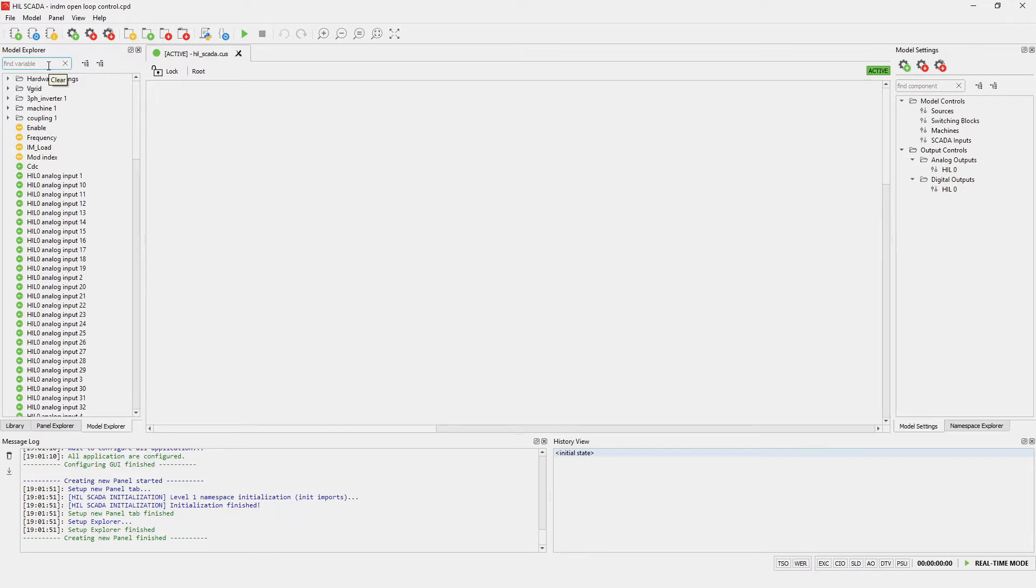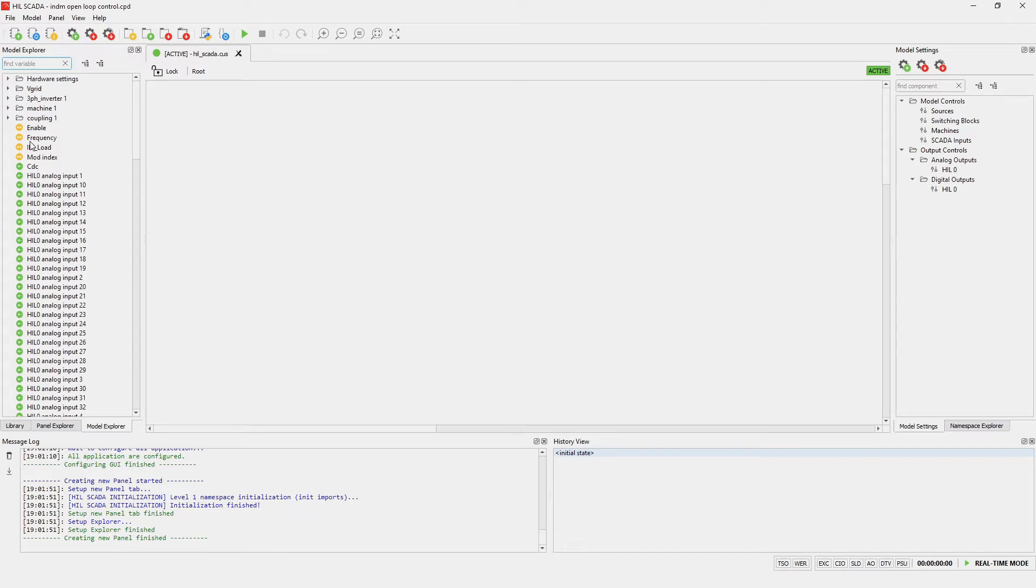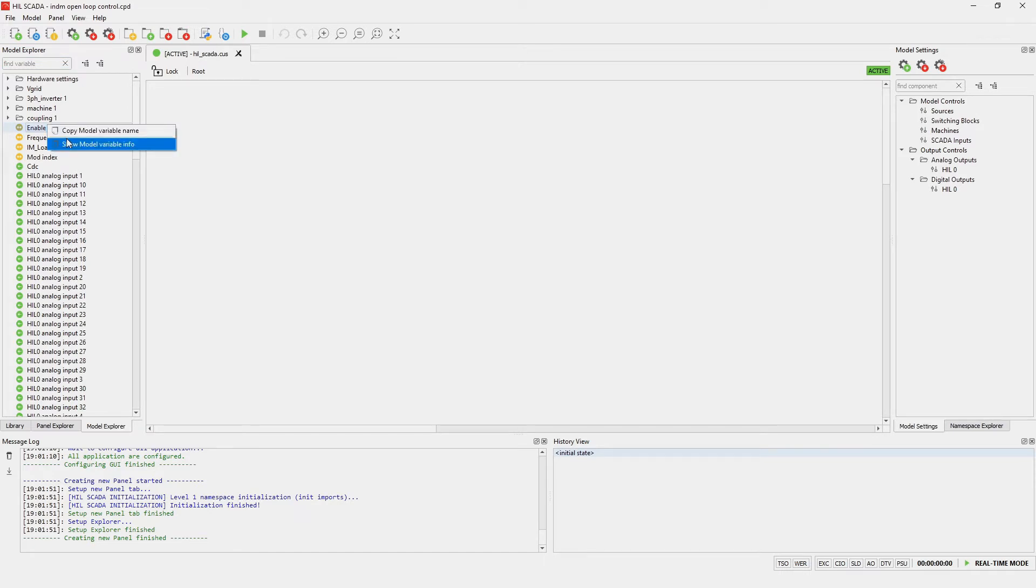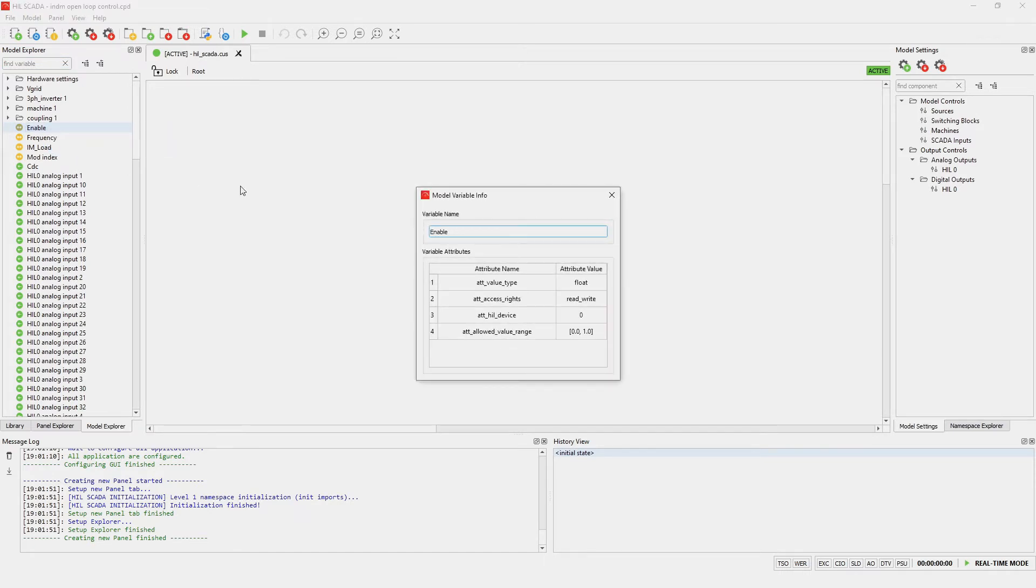It is worth mentioning that model variables that are colored green are read-only while the orange can also be used for sending commands. We can see model variable info by clicking right click on it and after that clicking show model variable info. Inside this dialog box we can see all the relevant attributes such as value type, in this case float, access rights, HIL ID and allowed values.